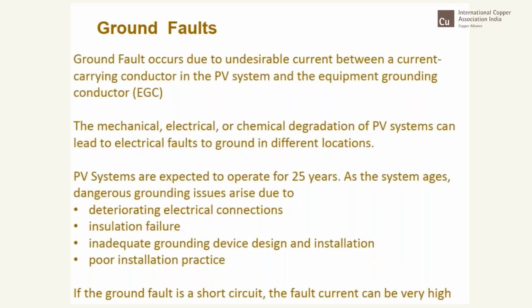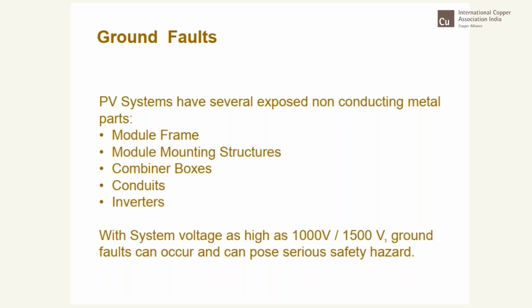Ground fault occurs due to undesirable current, and I don't have to explain what it is. The mechanical, electrical, and electrochemical degradation of a PV system can lead to electrical faults to ground in different locations. This could be because of deteriorating electrical connections, insulation failure, inadequate grounding device design and installation, and poor installation practice. So actually those causes which are responsible for arcing are also responsible for these. If a ground fault is a short circuit, the fault current can be very high. PV systems have several exposed non-conducting parts, such as the module frame. So if any ground fault takes place, then with all these metal combinations you have a problem, and also you are dealing with very high voltage.